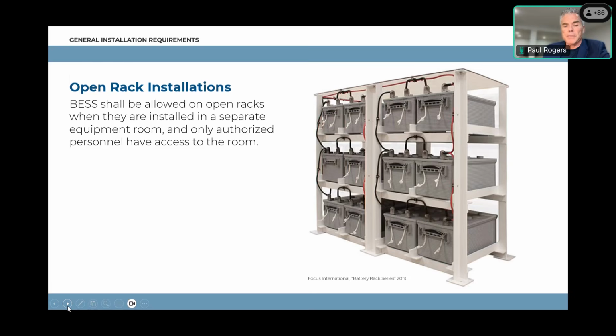Open racks—once again, we've seen these out there, and they are allowed. They're usually in a separate equipment room where only authorized personnel can get in. For those rooms, there should be some sort of signage on the front door for the fire department, and an electrical disconnect is important too—we don't want the fire department going in there without knowing what's involved and what chemistry is in that room. All of that should be incorporated into any installation with an open rack inside a room where only authorized personnel, or anyone, should be.